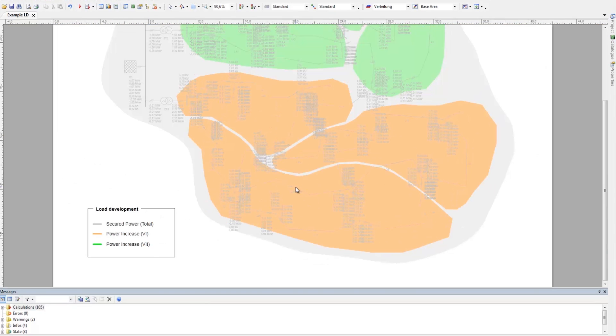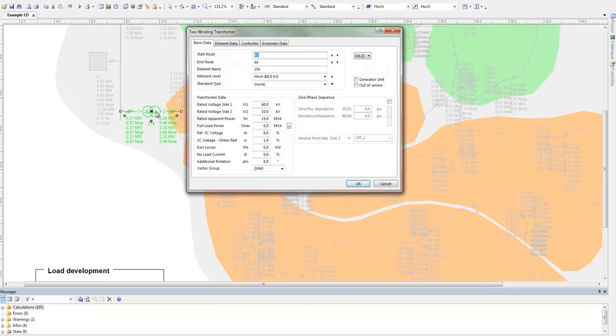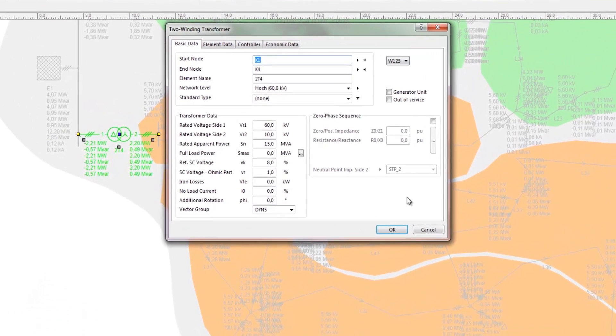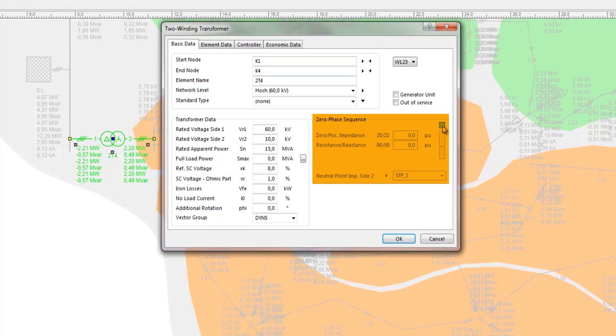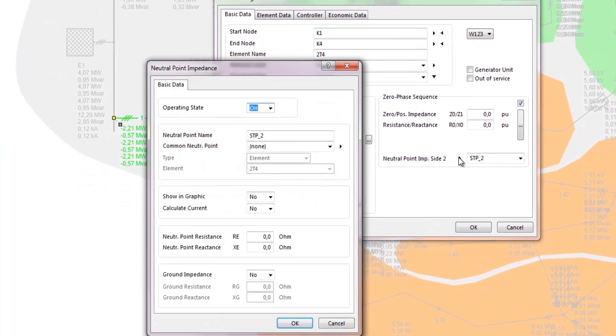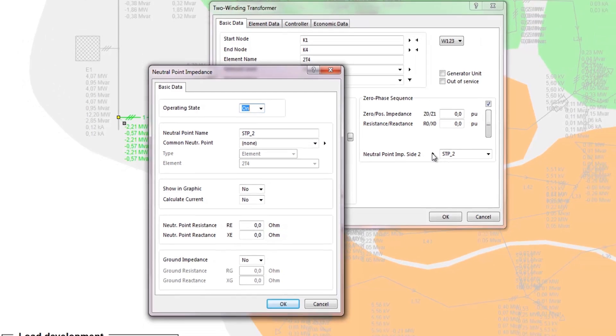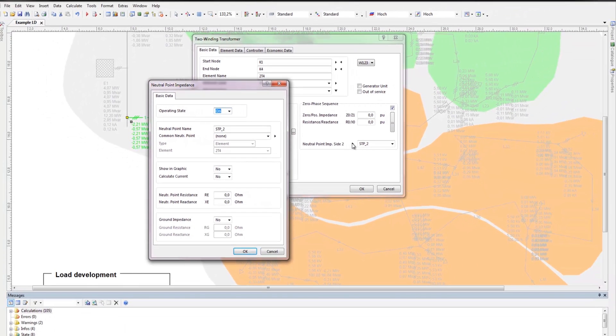Four-wire load flows can also be modeled in PSS SINCAL. Here, the return conductor and the transition from the return conductor to ground can be modeled, and the grounding impedances can also be modeled. The modeling of the return conductor is done with lines — either the zero-phase sequence can be defined as before, or the data of the return conductor is defined directly in the zero-phase sequence section. To model the connection of neutral points of network elements to the return conductor or to the ground, the neutral point impedance is available. The neutral point impedance can be assigned to generators, transformers, and even to nodes and bus bars.